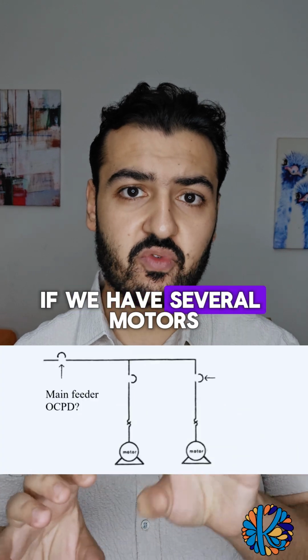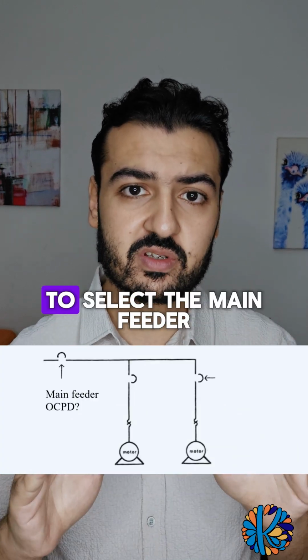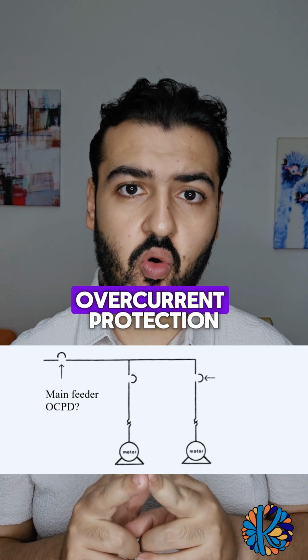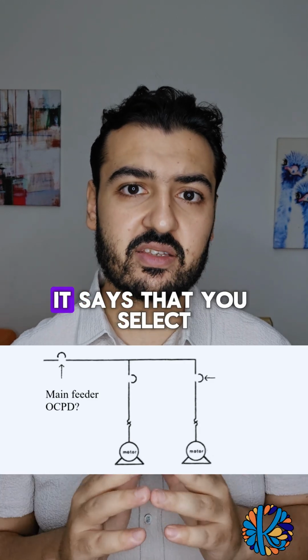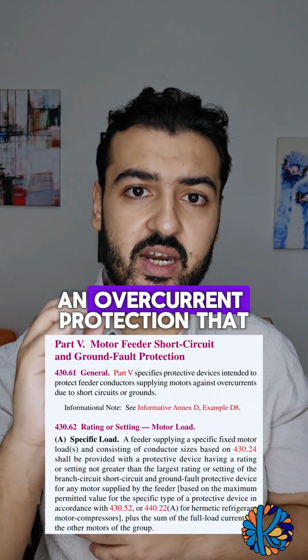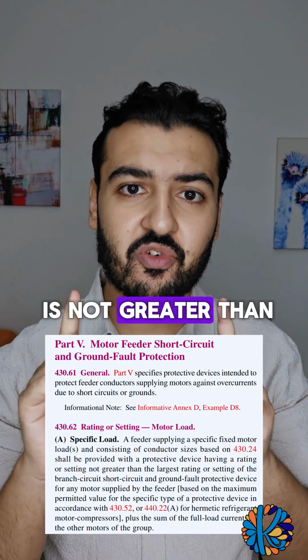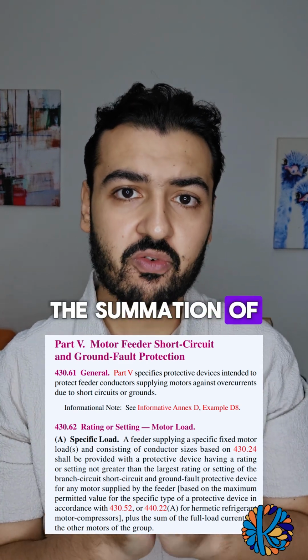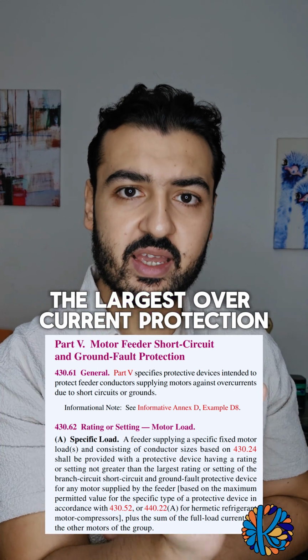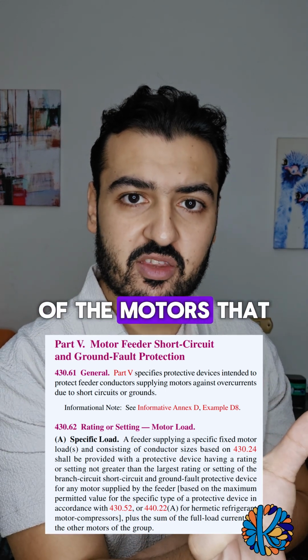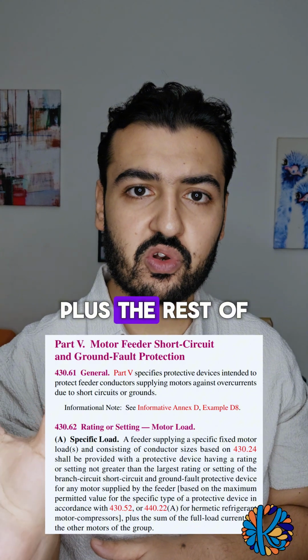If we have several motors and would like to select the main feeder overcurrent protection, NEC states that you select an overcurrent protection that is not greater than the summation of the largest overcurrent protection of the motors plus the rest of the full load currents.